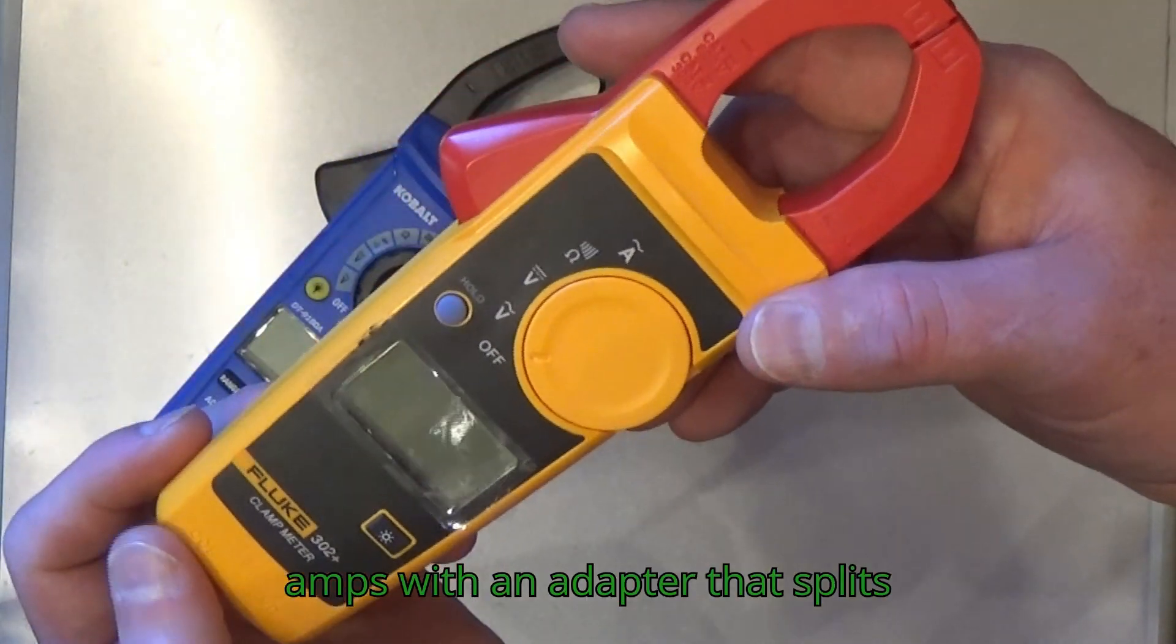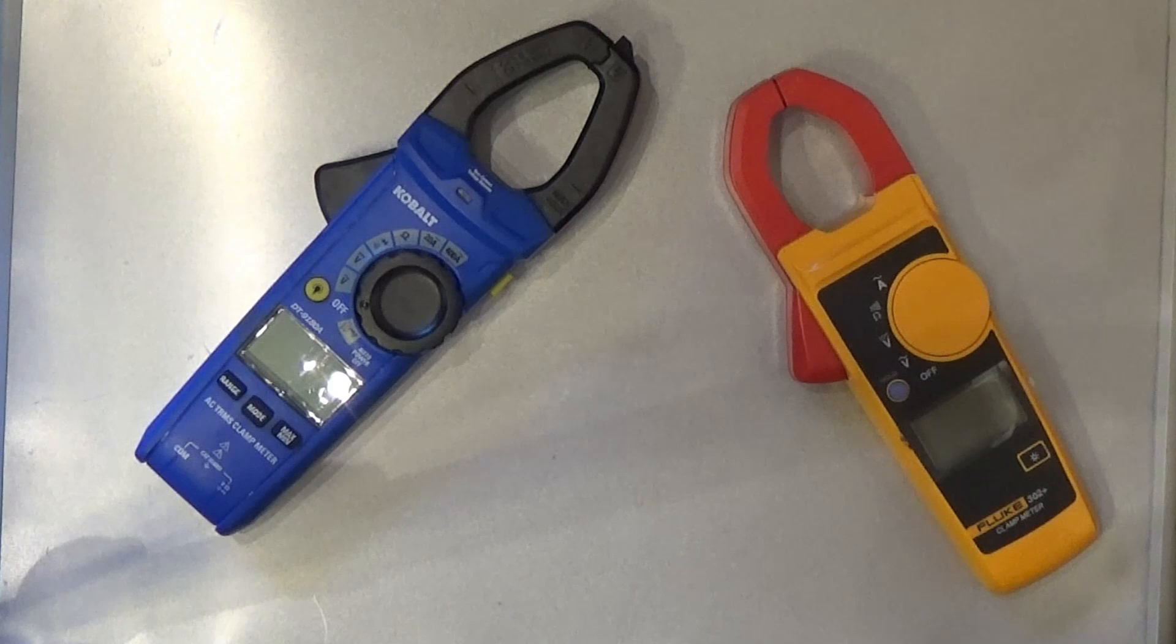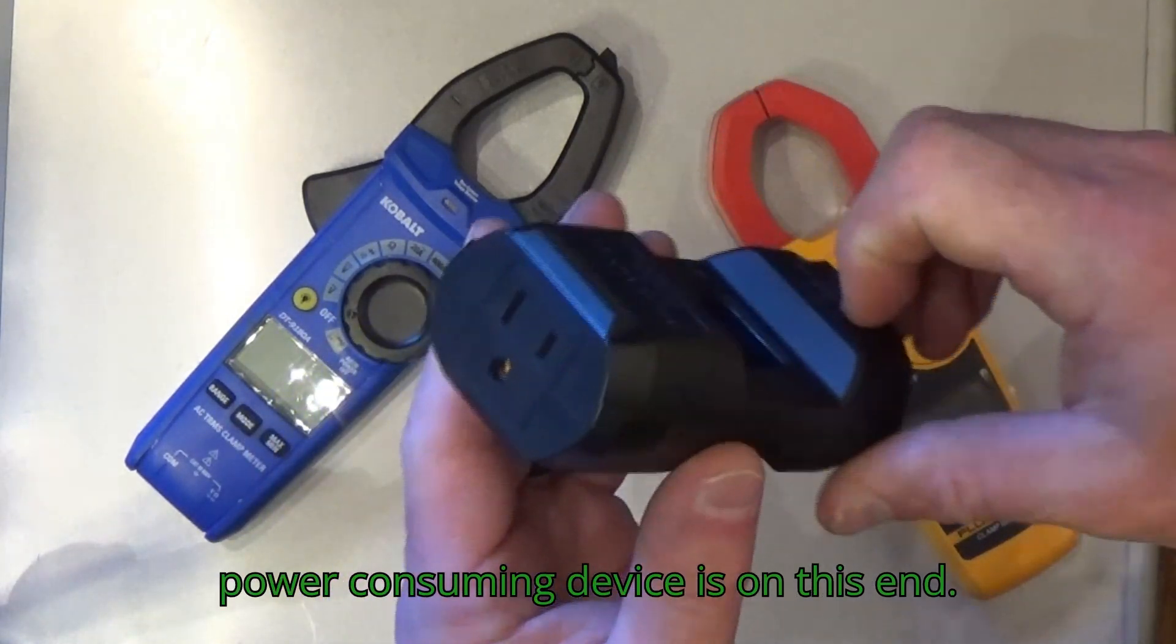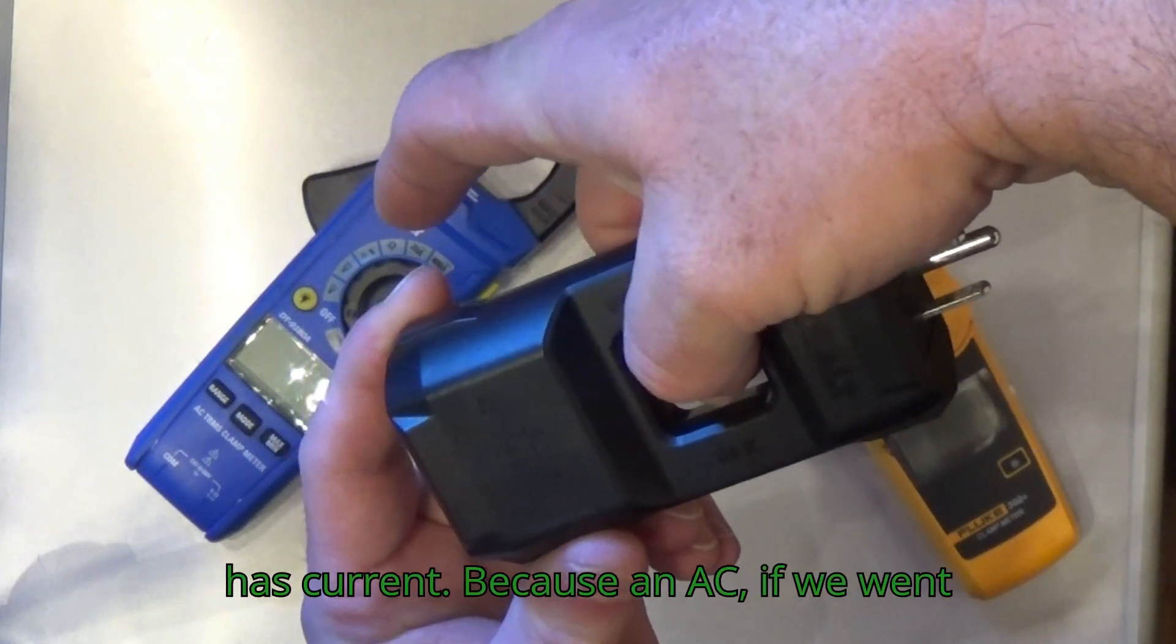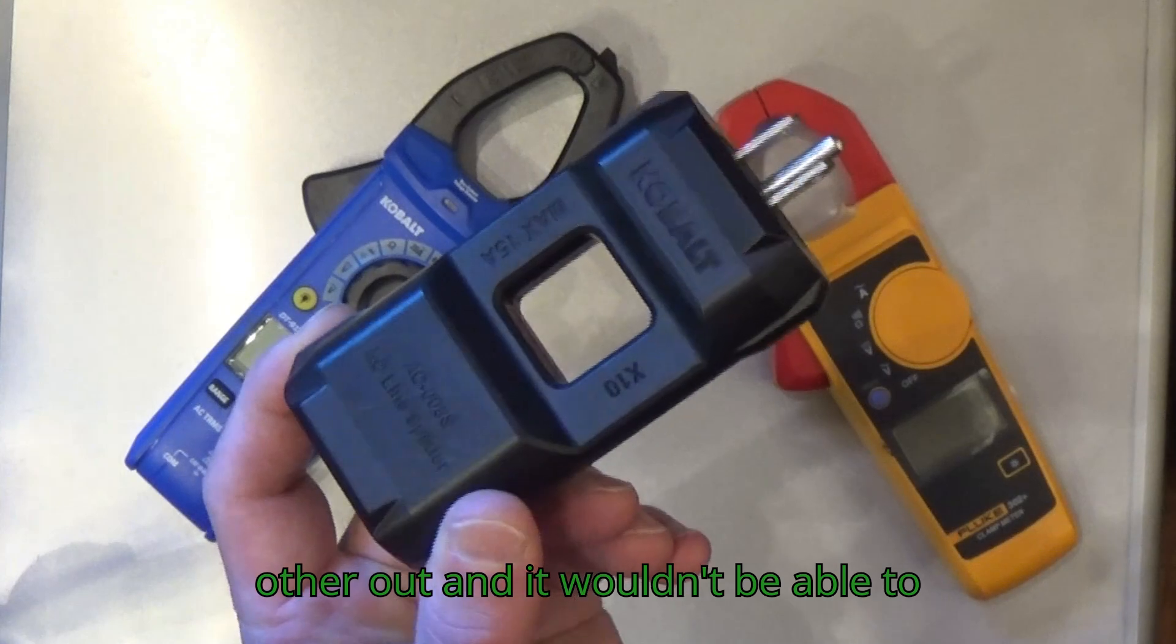What I'm going to do is show you how to measure amps with an adapter that splits a regular AC cable. It plugs in just like anything else, and then you plug in whatever the power consuming device is on this end. What happens is one leg goes through this side to the output, the neutral leg goes to the other side. This is how a clamp meter works: the meter goes around one leg that has current. If we went around both legs, that would cancel each other out and it wouldn't be able to measure current.